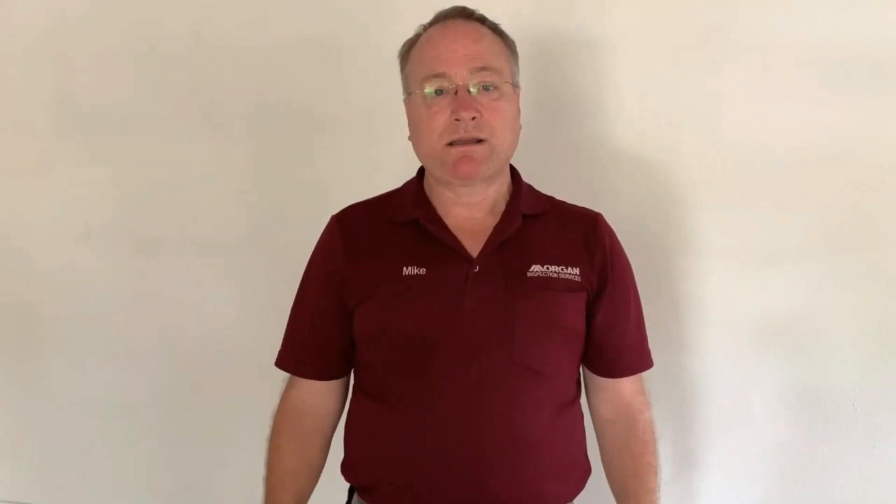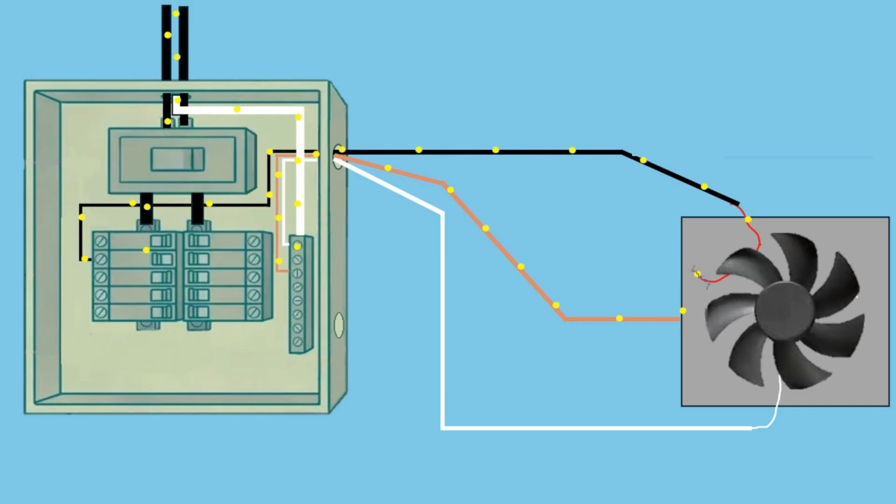So the very second that that wire comes loose and touches the frame a high current is sent back to the panel through that ground wire or the equipment grounding conductor and that causes the breaker to trip power to the washing machine and thus it's no longer a danger to electrocute people. So that's what grounding does for you.